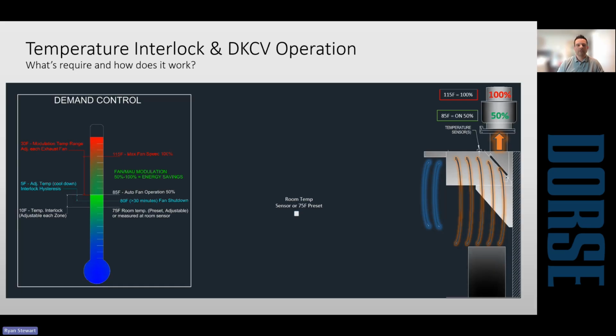And then it has a modulation temperature range. The factory setting is going to be 115 degrees, but that's adjustable depending on the appliance type. It's going to modulate airflow throughout the day based on what the temperature is underneath the hood. As far as shutdown is concerned, it wants to see the temperature drop 5 degrees below the activation point for 30 minutes before it shuts down. The idea behind it is they want to give the appliances time to cool, so when it loses exhaust, you don't short cycle the fan.